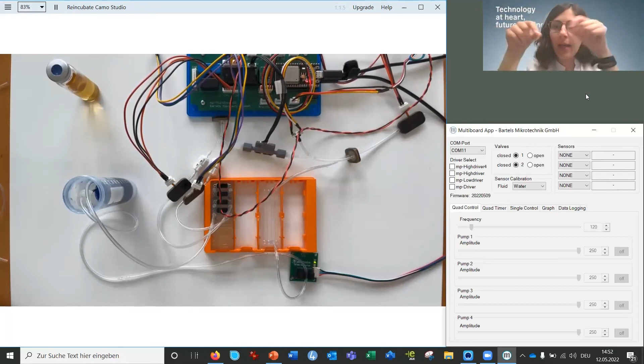By measuring the temperature difference between the two sensors once the heater is on, which is a micro heater engineered not to influence the measurement, we can determine the flow of the liquid inside, and also measure the temperature of the liquid. This sensor can also trigger alarms in case there's air in the line, such as bubbles, or an overflow if it exceeds what the sensor can measure.